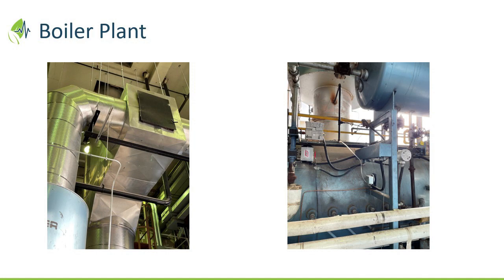Okay. Because you're not influencing combustion. You're just recovering heat energy. So in fact, the hotter the stack is, the worse it should be. So literally, and to Brent's point, most of you are flying blind. We used to cut costs on adding gauges and certainly technology to relay those points back to the front end a lot. That's only something we're doing routinely now in the last 10 years. So the only way you're going to know that is through temperature, and if it fails, you'll see steam. So you will see white. It looks like smoke, but it's steam. And so if the economizer fails, it's misting into the flue gas. It's changing phase into a vapor, and you'll see it in the stack.